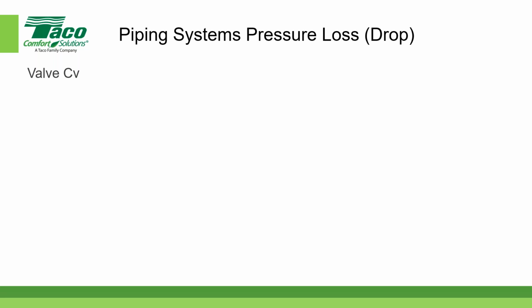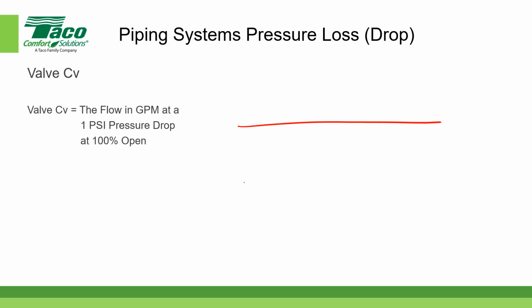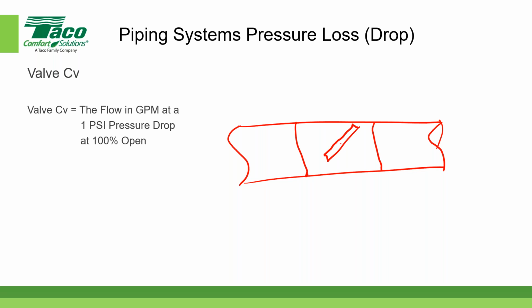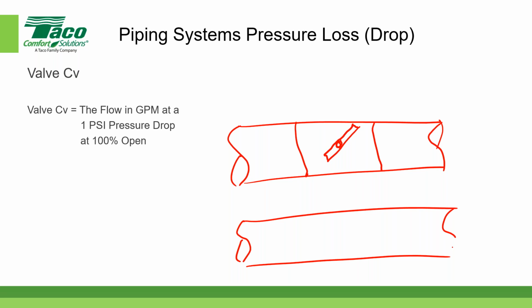Perfect. CV stands for valve coefficient, and by definition, the CV of a valve is equal to the flow in gallons per minute at a 1 pound per square inch pressure drop when the valve is 100% open. So for example, let's say I'm looking down from the top at a piece of pipe. Does that look like pipe, Brett? It does. Okay. Let's say I have a butterfly valve in this section of pipe, and the butterfly valve is partially open, so it might be at an angle like that. I can look at that same set of pipe again, making a quick sketch here. This time, the valve is 100% open because it's parallel to the flow of the water. Sometimes we call it the wafer or the disc as part of a butterfly valve.